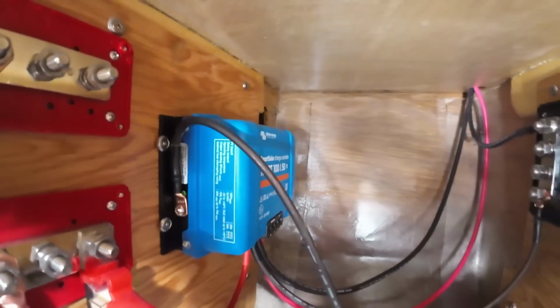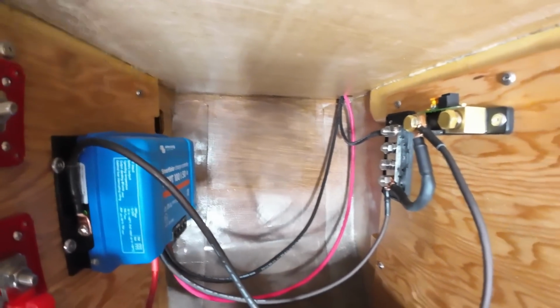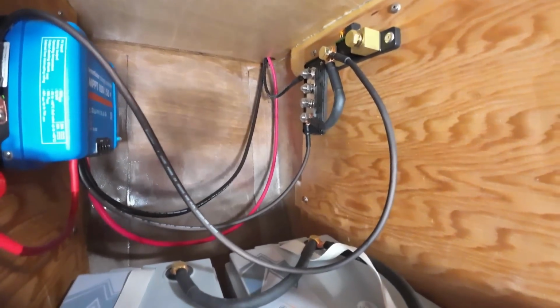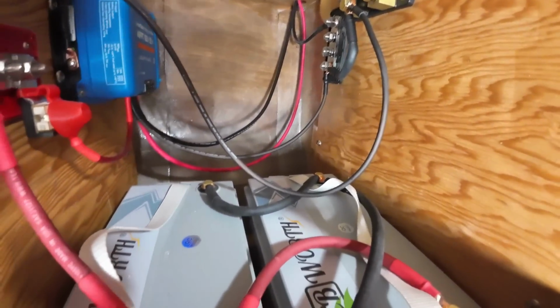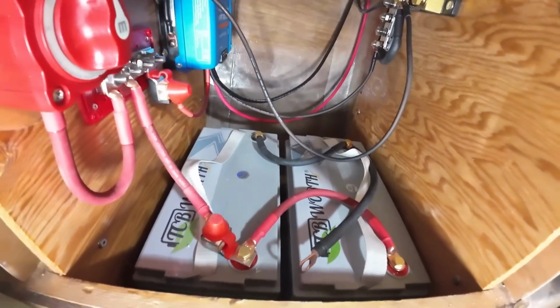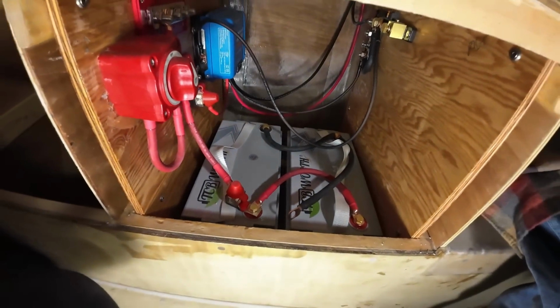So are we the correct wire gauge, or are we actually oversized on our wire gauge? For the batteries, two wire gauge there, but we have 6 wire gauge for the wires coming into the MPPT, which are oversized.